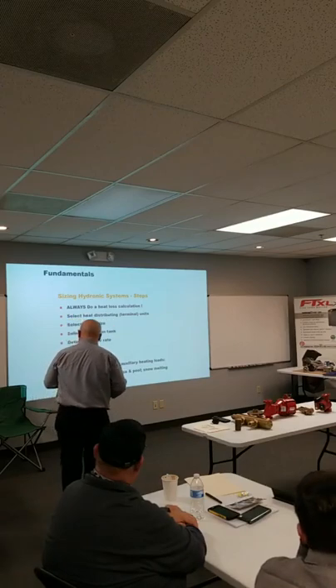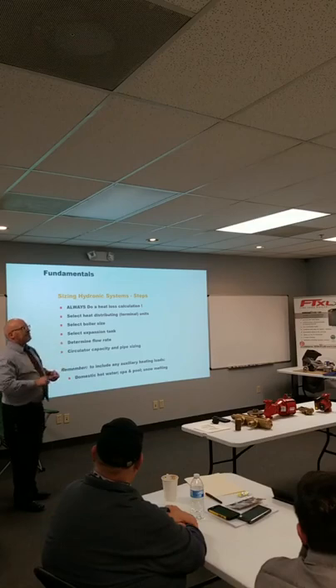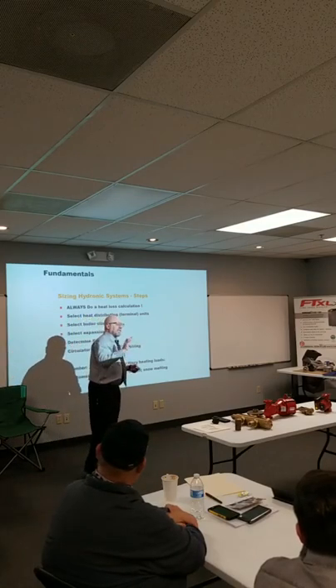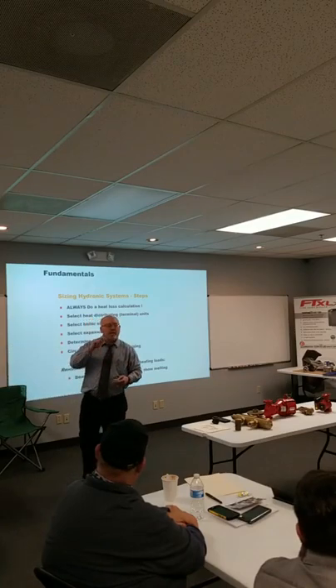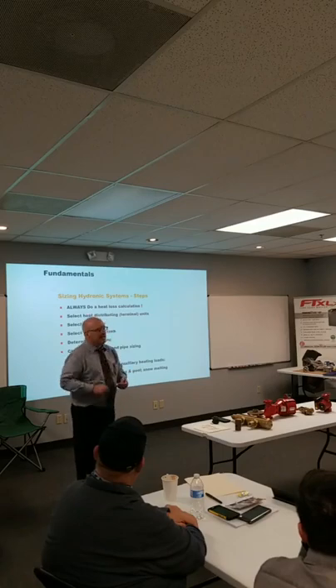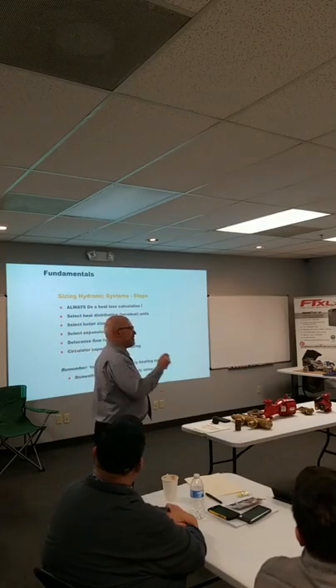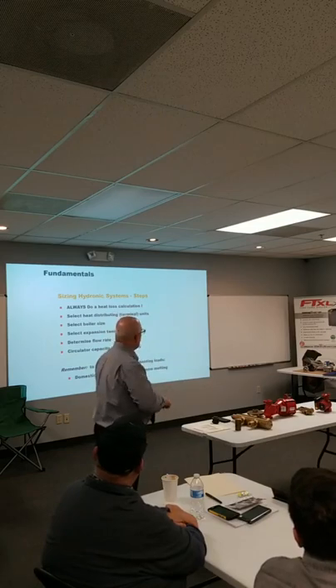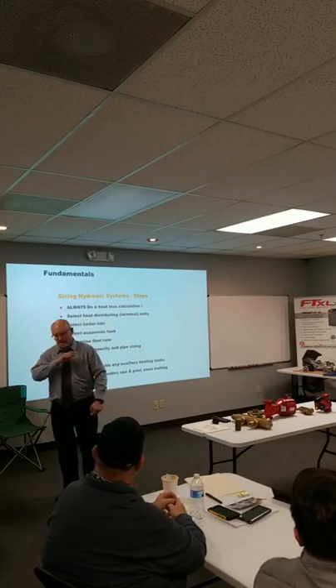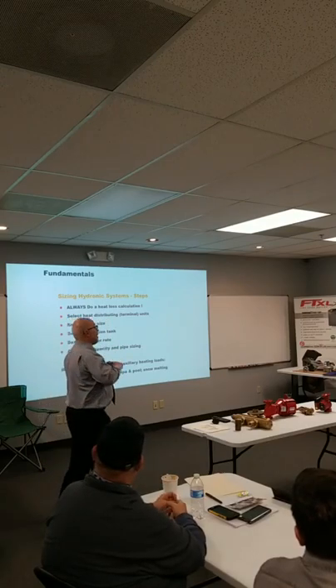But how do we replace boilers today? You look at the BTU rating and they swap it out with a high efficiency. I like that, but why are you doing that? I hear that a lot. They say that's what we want to do because it's got a 10-to-1 turndown on it, it's much more forgiving. I'm going to tell you it's more critical to size a condensing boiler than it was the old boilers, because now I've got blowers, sensors, controls, all kinds of things.